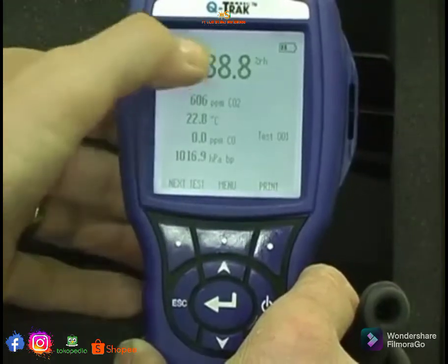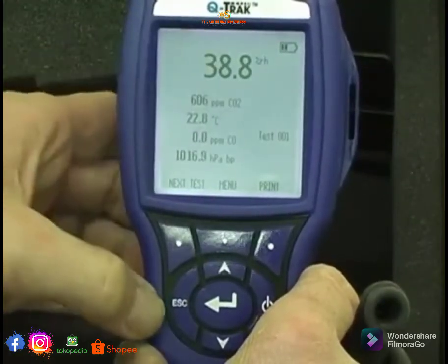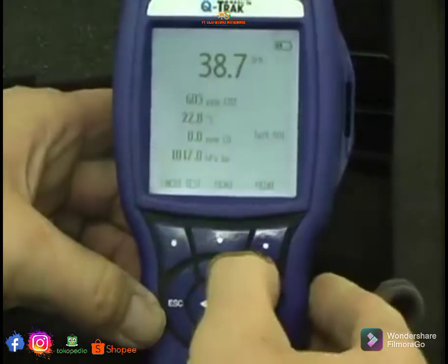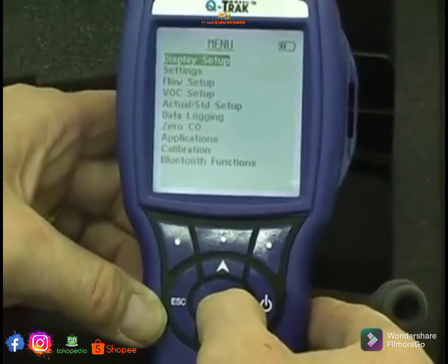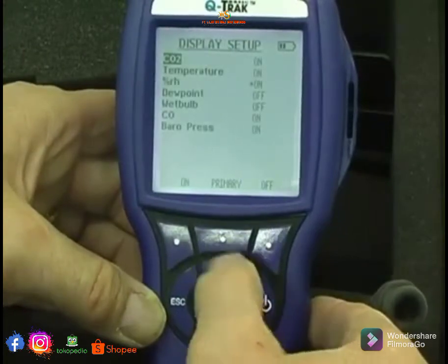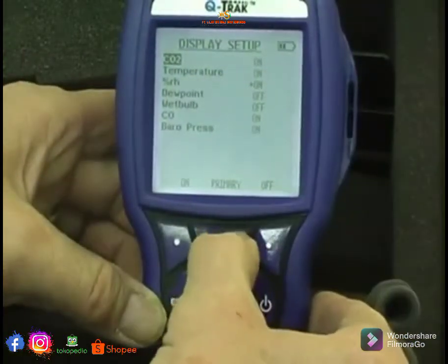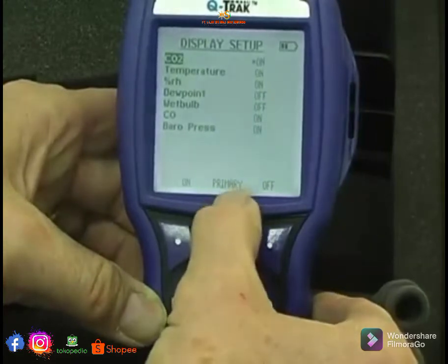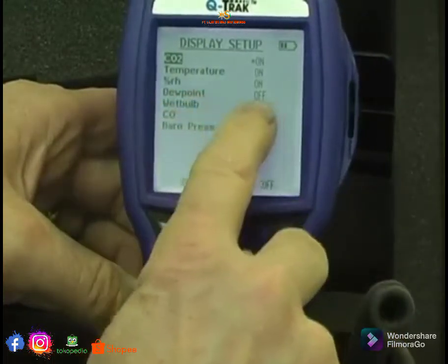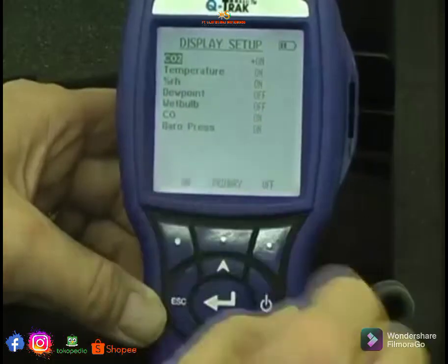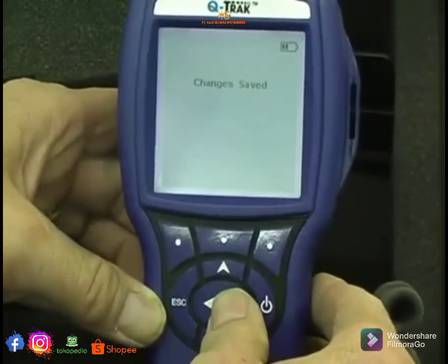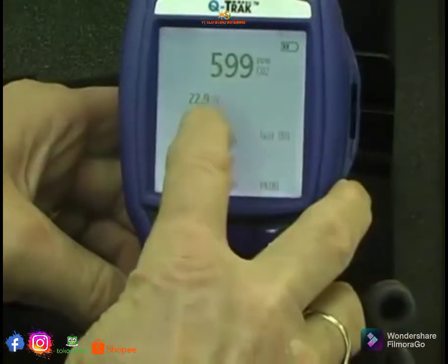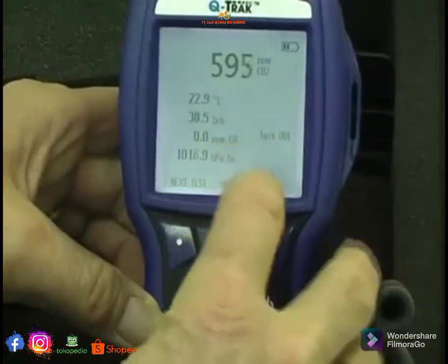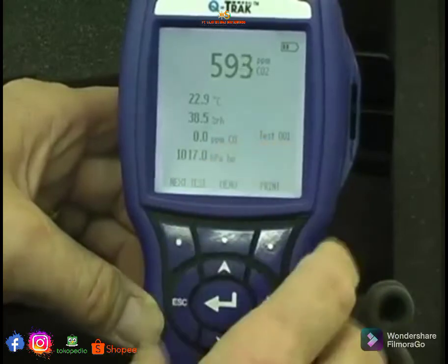Now at the moment this instrument is set up as displaying RH as the main figure. We can change how this menu is operating very easily here. We hit the menu key, then I hit enter to go into display setup. Now I want to make CO2 the primary display, so I hit primary display. We don't need to show dew point or wet bulb, we're happy with everything else. Now I hit enter to save it, and escape to go back. Now you notice it's got CO2, temperature, humidity, carbon monoxide and the air pressure.